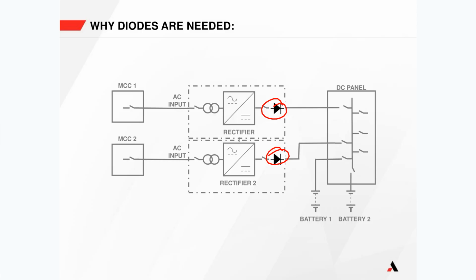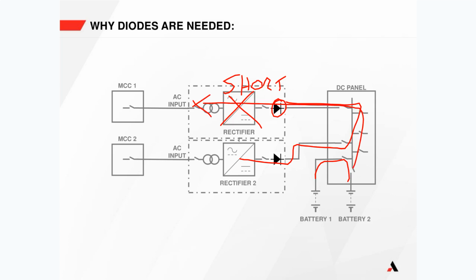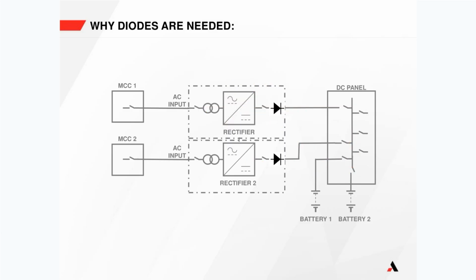The good thing these blocking diodes do is if you have a fault inside this rectifier - let's say there's a short inside it - we cannot feed current from the other charger or these two batteries back into that short, because this diode says, nope, I'm not going to allow current to flow this way into my short. So it protects the system from feeding current into a faulty system in a redundant setup.